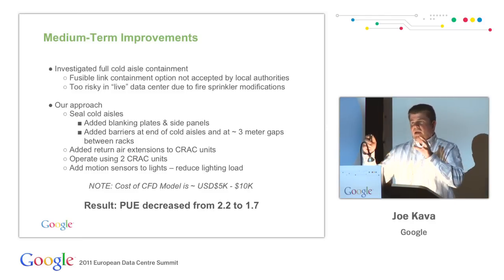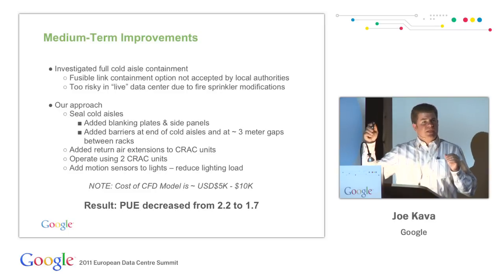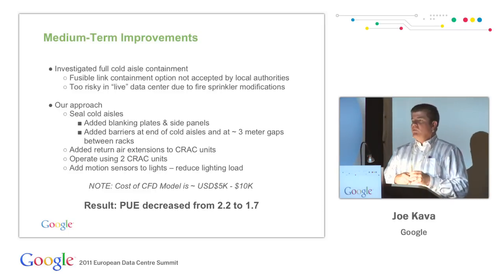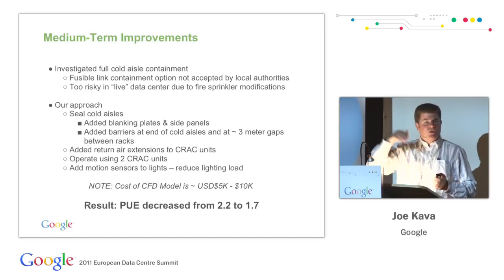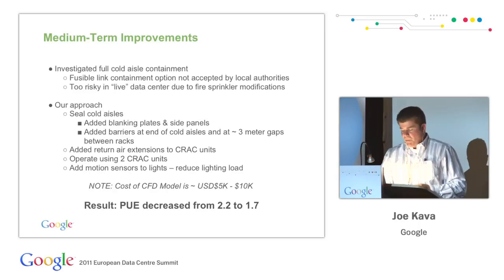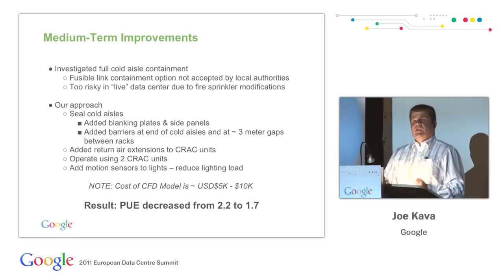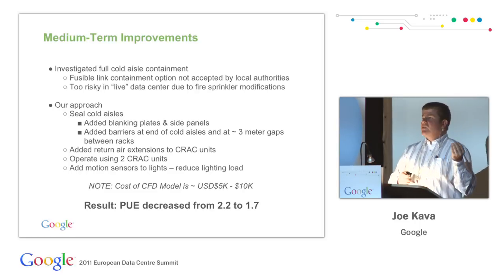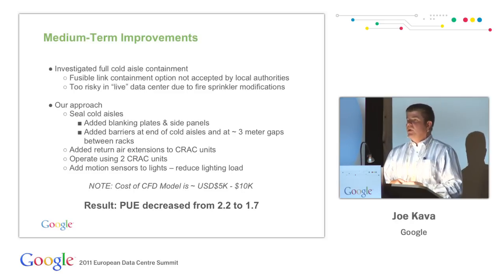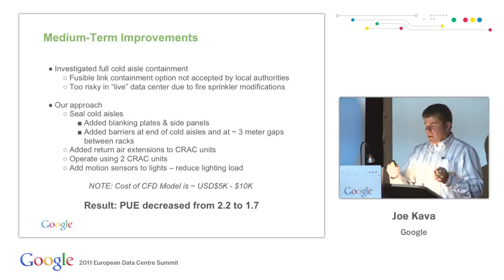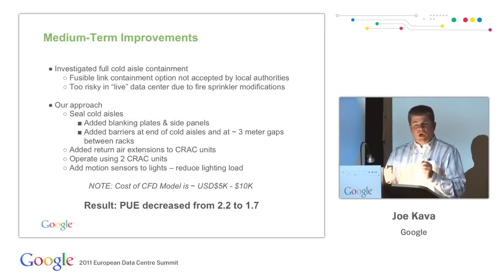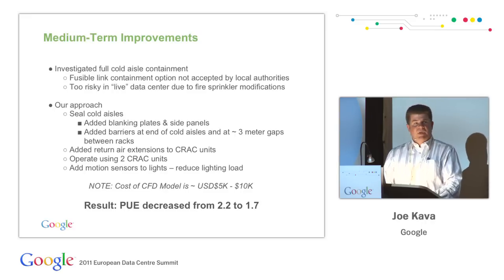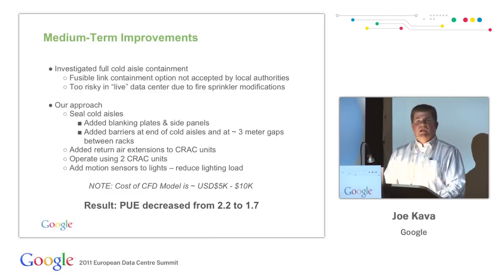We also fitted 1.2 meter tall return air extensions onto the CRAC units, and that was to prevent the warm air from discharging directly into the CRAC air intakes. And we also did some things with the lighting load. We implemented automatic sensors that would turn off the lights when the rooms were unpopulated. You know, simple things like that. But they were low cost, easy to do, and we modeled all of this with our CFD modeling. I mentioned we have this capability in-house. If you don't, it can be easily contracted out for a very modest amount of money, around $5,000 or $10,000, you can get good CFD modeling done.